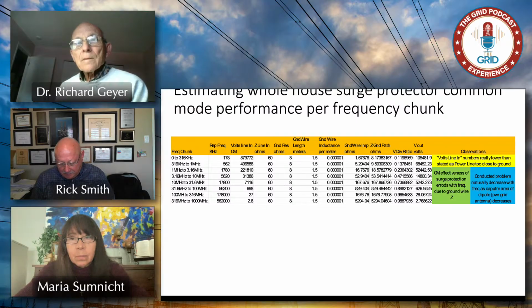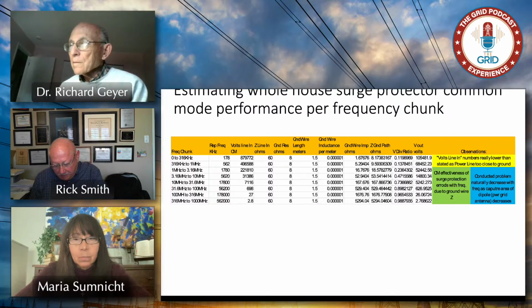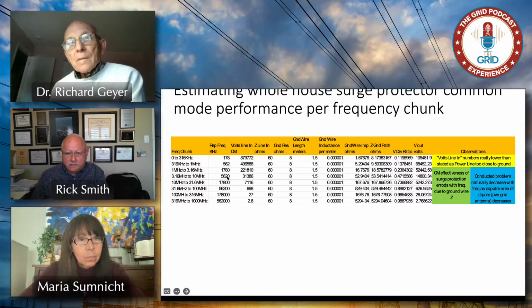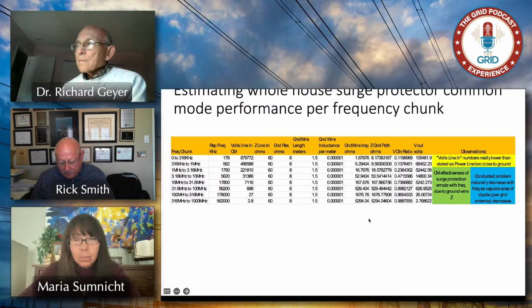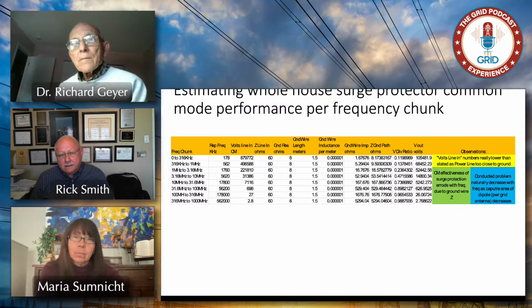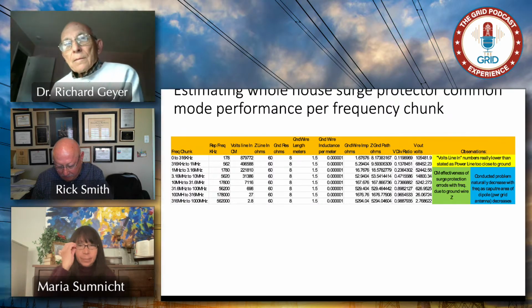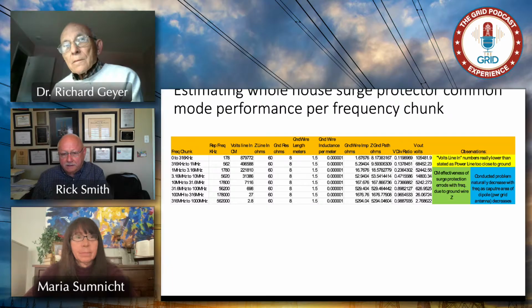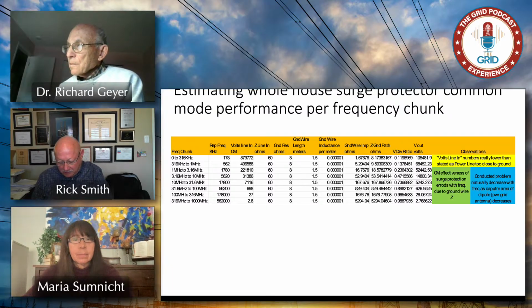But as you go further up in frequency, pick 5.6 megahertz, which is still relatively low considering the spectrum goes all the way up to 1,000 megahertz, your effectiveness has dropped from around 20 dB to around 6. So you're basically letting half of what came in go out, because you're getting increased impedance in that wire going to ground. Finally, just to be ridiculous, at 562 megahertz, 98.8% of the voltage that came in gets passed right on to you. So your surge protector is not helping you at all at that point, with respect to common mode.